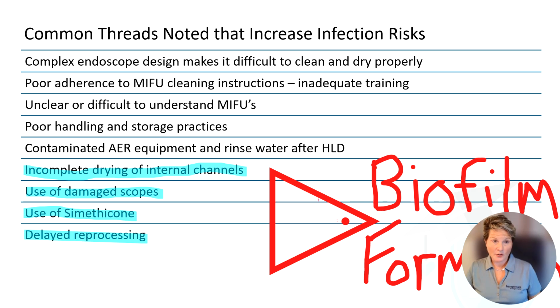The use of damaged endoscopes. Now, any kind of damage on any kind of scope surface is going to act like a reservoir for bacteria and gunk and whatever to get caught up in there. And so if we don't know that we're using damaged scopes, we don't know that this is happening, and it makes it really hard to clean. And then the use of simethicone is another really big issue. I know the doctors love it. It really works great for getting rid of those bubbles during the procedure, but it really sticks around on the endoscopes, and it's incredibly difficult to remove even after multiple rounds of HLD.